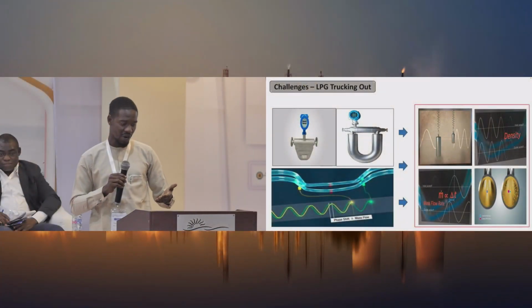One of the problems is this. When building an LPG or any gas system, try as much as you can not to have a long pipeline network from your storage to your dispensing point. That is a very big problem for you, and you have to battle it. But regardless, after battling a lot, we had to find a way to, once in a while, solve this problem. So our tank to our loading gantry is about 250 meters, which is a lot for product movement.